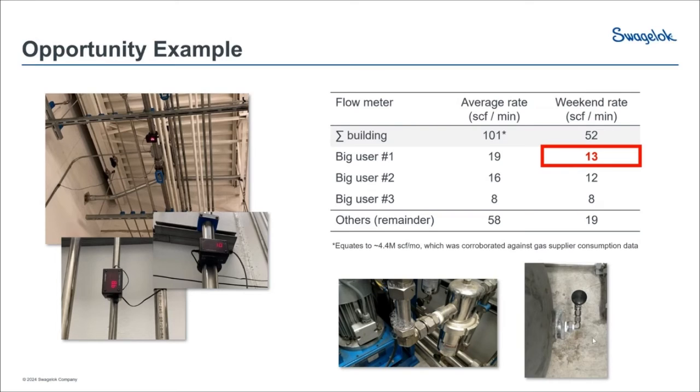but it wasn't the 12, 13 that we were measuring. And I think that that's really important because the customer was able to prove, contrary to their suspicions, that it actually wasn't the leaks that were causing the problem. And what that informed the customer, or helped them to then realize, is that it must be due instead to some of their constant purging that they have tied to those gas systems with equipment inside that sub-facility.